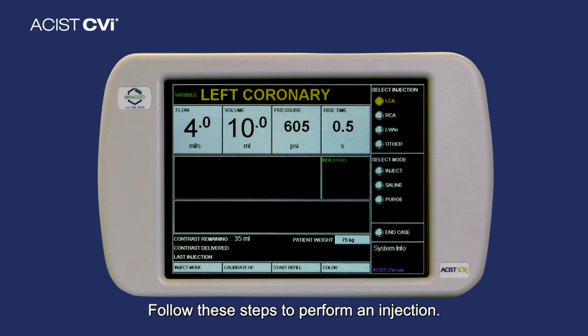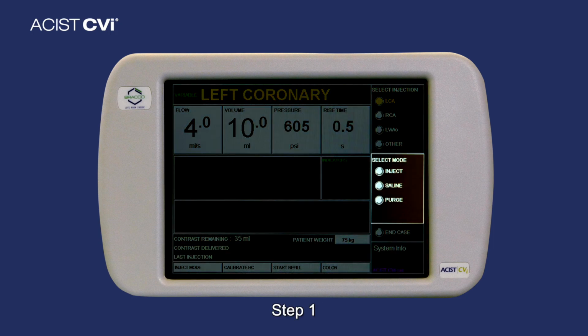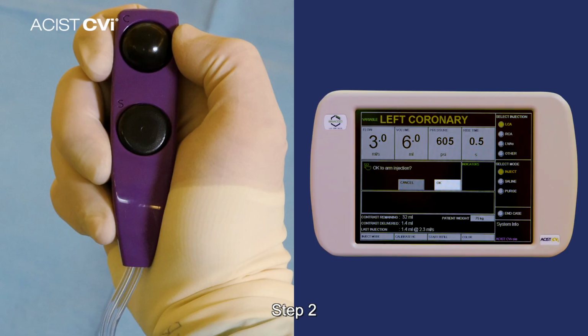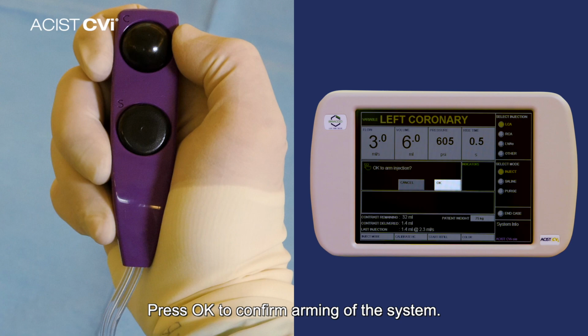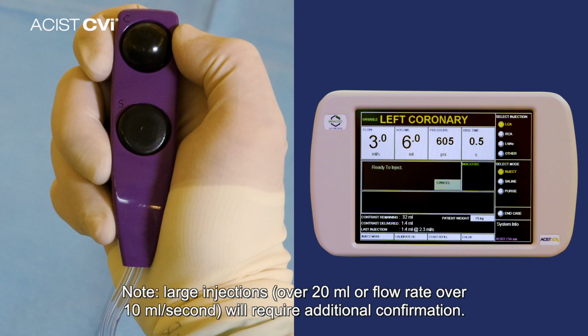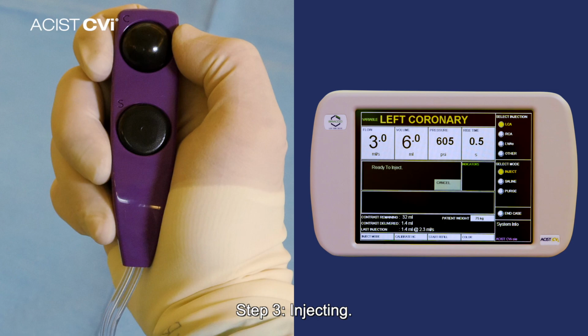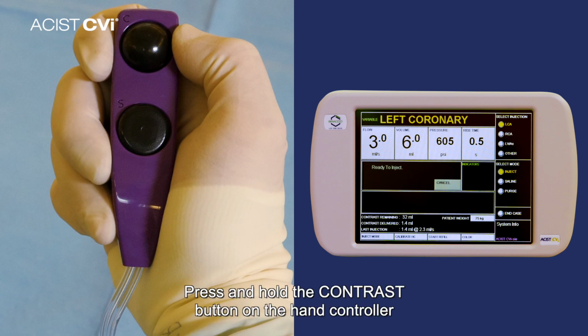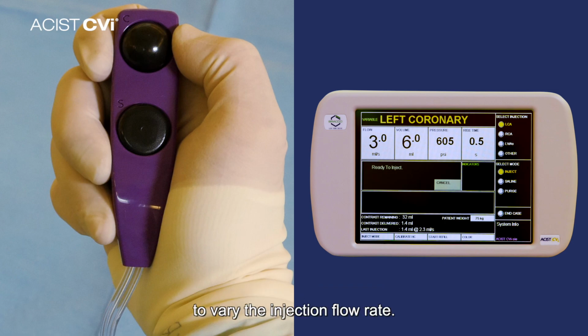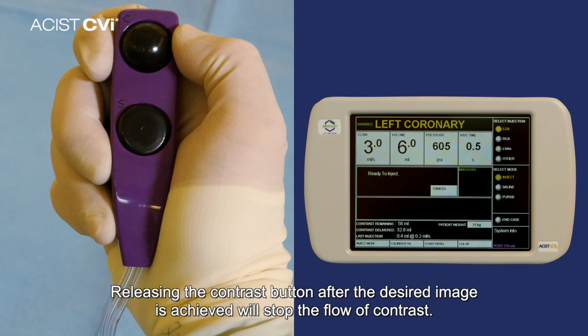Follow these steps to perform an injection. Step 1. Arm the injector. In select mode, press Inject. Step 2. Press OK to confirm arming of the system. Note: large injections over 20 ml or flow rate over 10 ml per second will require additional confirmation. Step 3. Injecting. Press and hold the contrast button on the hand controller to vary the injection flow rate. Releasing the contrast button after the desired image is achieved will stop the flow of contrast.